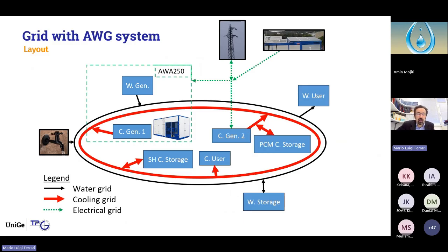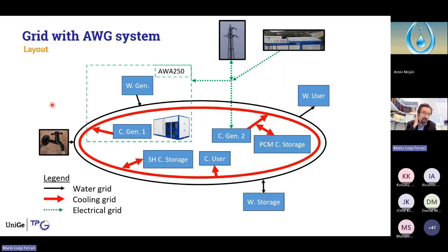In this work, I would like to present the grid that has been taken into account. It is based on water grid. Water can be obtained from the aqueduct, or can be obtained from an AWG system, the AWA250 by GEAS, able to produce both water, clean water, and cooling water for the cooling energies, the cooling demand satisfaction. So we have also the cooling grid. The cooling grid includes for sure the generation from the AWA250, but also the generation by the cooling side of a heat pump that is based on butane. It is a heat pump available in our laboratory. It is an 11 kilowatt electrical power heat pump.